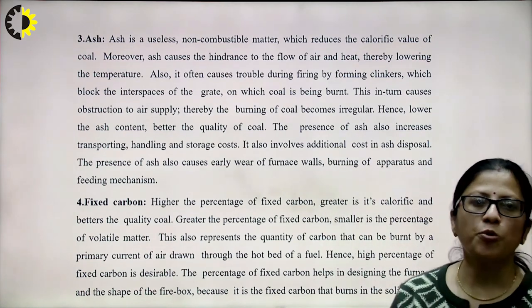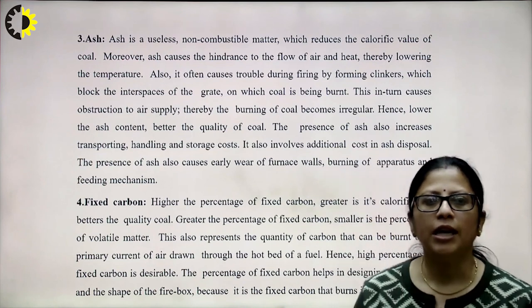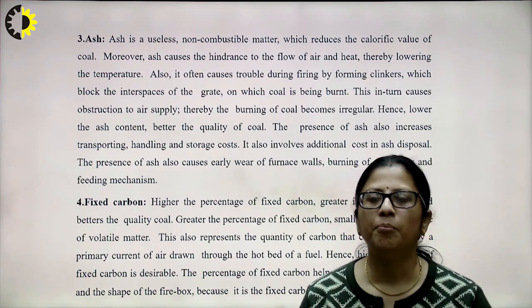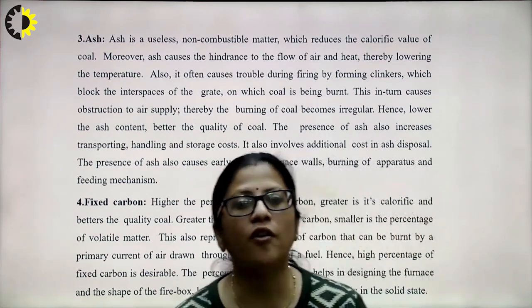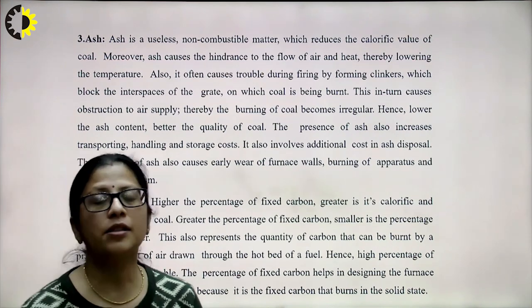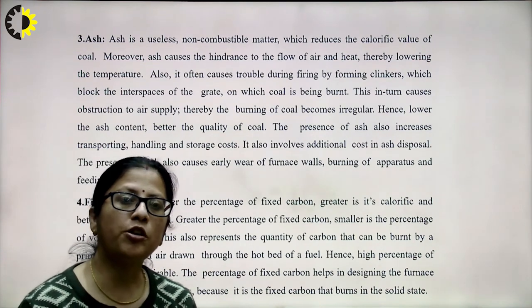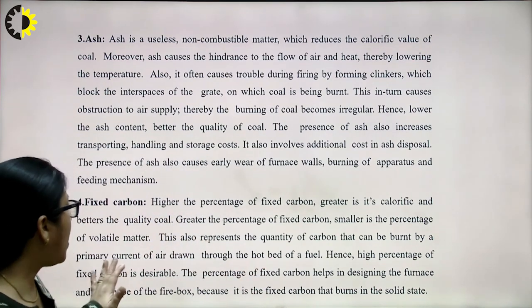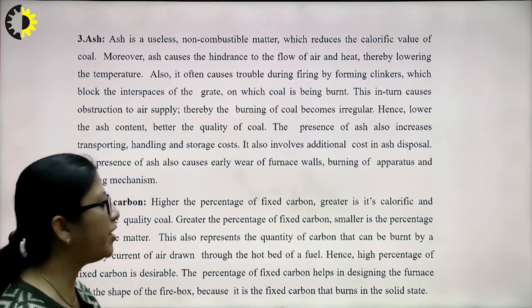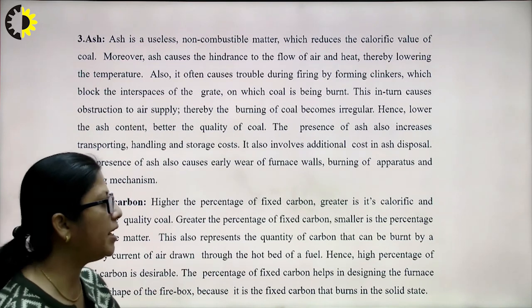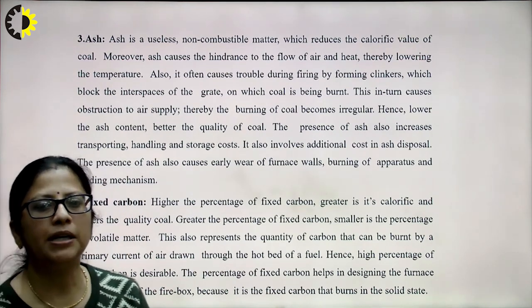Ash disposal adds cost and causes early wear of furnace walls and feeding mechanisms. Regarding fixed carbon: higher percentage of fixed carbon means greater calorific value and better quality coal. Greater fixed carbon also means smaller percentage of volatile matter. It represents the quantity of carbon burned by a primary current of air through a hot fuel bed, so a high percentage of fixed carbon is desirable. The percentage of fixed carbon also helps in designing the furnace and firebox shape, since fixed carbon burns in the solid state.